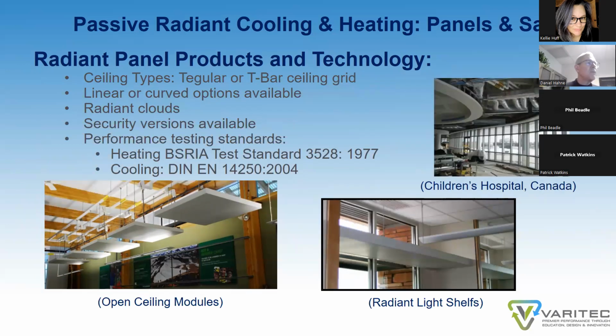Radiant panels can actually fit in tegular or T-bar grids. They can come in linear or curved options. They can make radiant clouds within a space, as well as an architectural feature that actually lends itself to the HVAC system. You can provide these devices in secure environments as well. One of the things you want to make sure of, if you're designing to it, is that you have the proper independent testing and standard for these devices to secure confidence that the manufactured product has the heat transfer that it proposes to have.